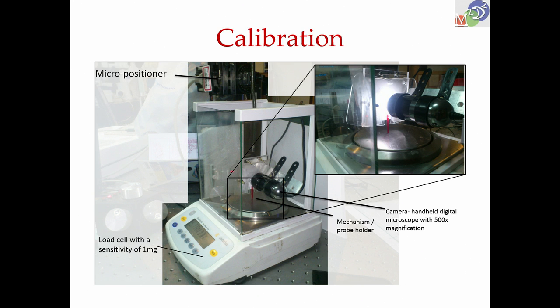In this particular case study, the challenge was actually in calibration. We want to measure micronewtons, but we need to have a sensor that can measure micronewtons and then say that our sensed value is correct. Here that was a big challenge, because there was no other force sensor. What we ended up doing was go to a very sensitive balance and put the probe there, see whatever it shows, and compare with what we get. That is what we have to do.